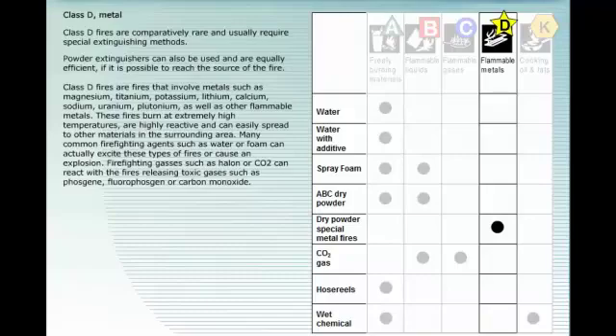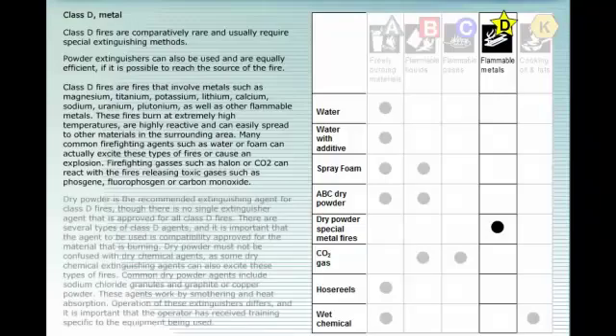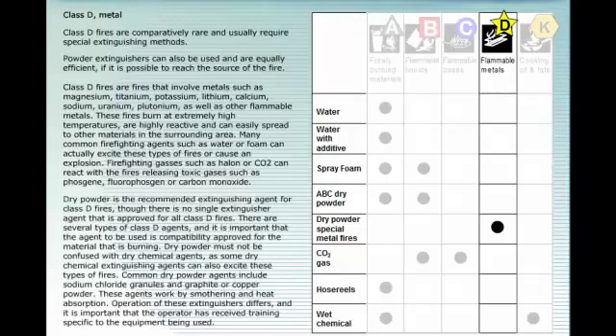These fires burn at extremely high temperatures, are highly reactive, and can easily spread to other materials in the surrounding area. Many common firefighting agents such as water or foam can actually excite these types of fires or cause an explosion. Fire fighting gases such as halon or CO2 can react with the fires, releasing toxic gases such as phosgene, fluorophosgene, or carbon monoxide. Dry powder is the recommended extinguishing agent for Class D fires, though there is no single extinguisher agent that is approved for all Class D fires. There are several types of Class D agents, and it is important that the agent to be used is compatibility approved for the material that is burning. Dry powder must not be confused with dry chemical agents, as some dry chemical extinguishing agents can also excite these types of fires.